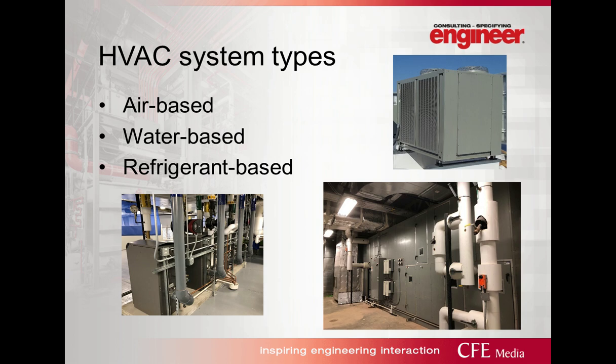The next system is water-based, typically referenced as hydronic systems. These systems might be hot water baseboard heat, in-floor radiant heating, in-floor radiant cooling systems, ceiling radiant cooling systems, or chill beams. Of course, the next option is a combination: an air-handling unit with hot water and chilled water coils combined with a chiller and boiler plant. The hydronic system may also serve perimeter heat or VAV box reheat. The final basic HVAC system is a refrigerant-based system, typically referred to as VRF — variable refrigerant flow — or VRV (variable refrigerant volume), which is specific nomenclature to a manufacturer's branding.